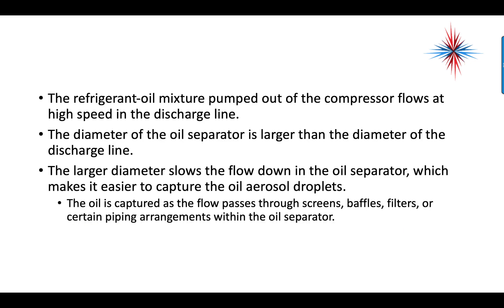The refrigerant-oil mixture pumped out of the compressor flows at high speed in the discharge line. The diameter of the oil separator is larger than the diameter of the discharge line. This larger diameter slows the oil flow down in the oil separator, which makes it easier to capture the oil aerosol droplets. The oil is captured as the flow passes through screens, baffles, filters, or certain piping arrangements within the oil separator.